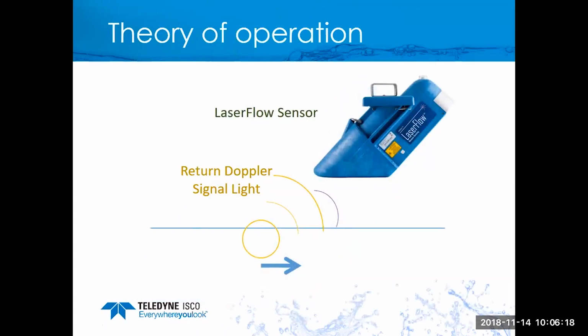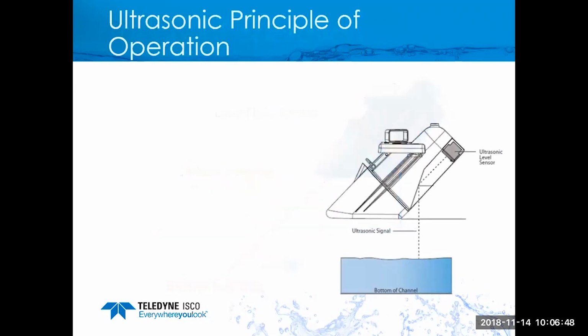So let's talk about the theory of operation of the laser. There are two main components to the laser. One is an ultrasonic sensor, and it is mounted in the back of the laser. It transmits a signal, reflects off a deflector plate, hits the surface of the water, and knows where the water is. Once it knows where the water is, we focus the laser below the surface. So we take a measurement to know where the water is, we focus the laser, and that's where we get our signal back. This is the patent of the laser.